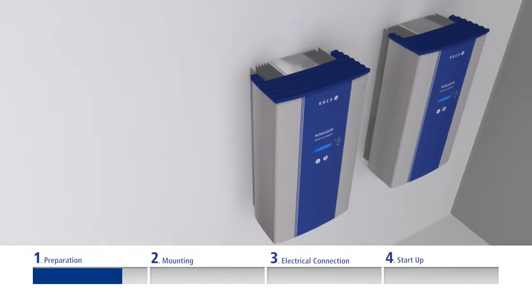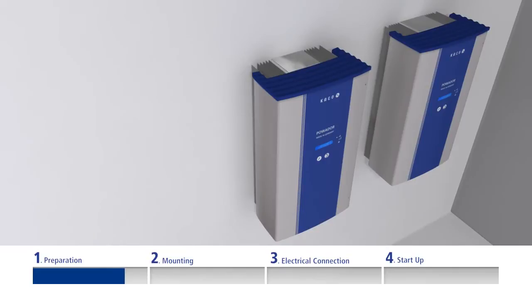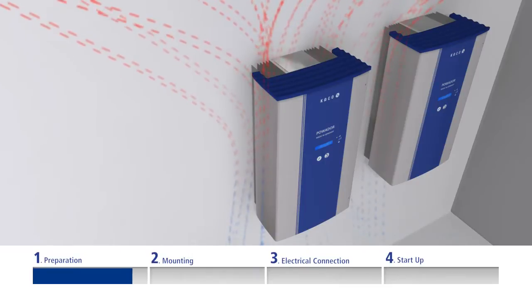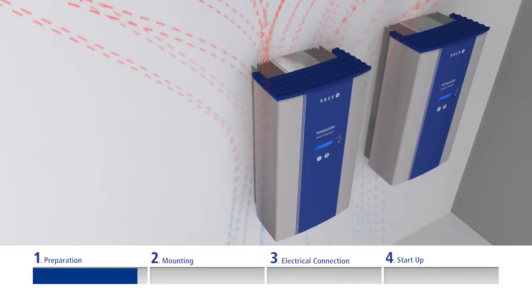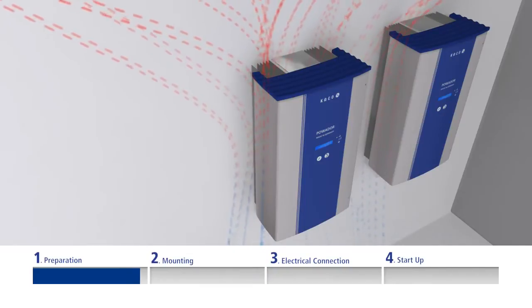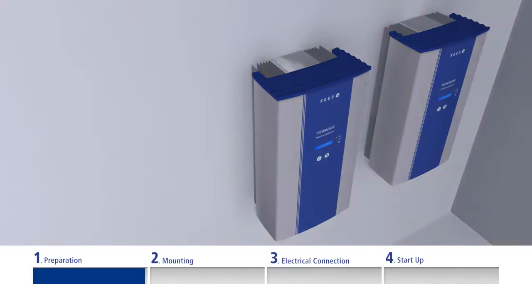The inverter heat sink may reach a temperature of up to 90 degrees Celsius or 194 degrees Fahrenheit. Therefore, only mount the inverters on walls made from heat-resistant materials and ensure that air can circulate freely around the housing and through the heatsink on the rear side.